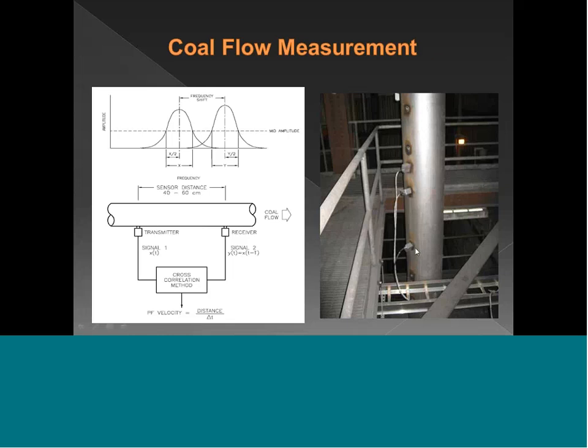What we do with the same two antennas is we look at a fingerprint of the coal particles electrostatically as they move past this sensor and this sensor. And we mathematically cross-correlate them. So we can know when the material that was here, or the bulk of the material that was here, is now here. And we simply note the change in time. The distance is the spacing between the sensors, the change in time being how long it took to see the comparison. Distance over time is speed. So we very accurately know the speed. Through the course of this hour presentation, I'm also going to talk about how important that speed is to combustion optimization. It is equally as important as the mass flow of coal moving through a pipe.